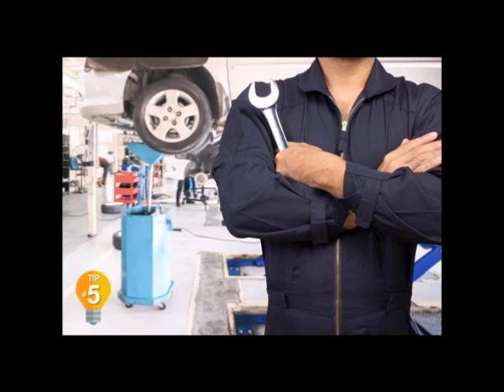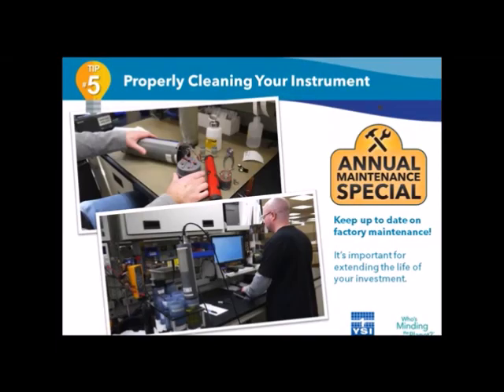So think of this like your car's tune-up. The mechanic's going to change out your belts, lube fittings, and make recommendations based on the diagnostic analysis. When you send your water quality instrument back for a preventative checkup, an expert technician will inspect items like internal O-rings, internal torque adjustments. They'll perform power consumption tests, pressure tests, and specification testing of the system. I believe there may be a maintenance special going on right now, so check the website for details.